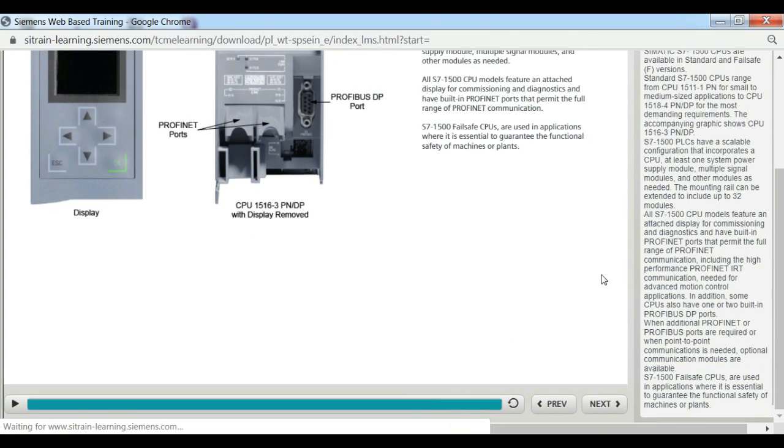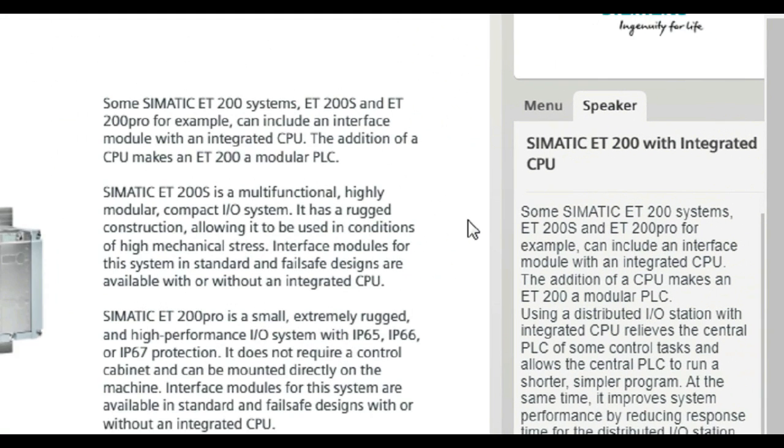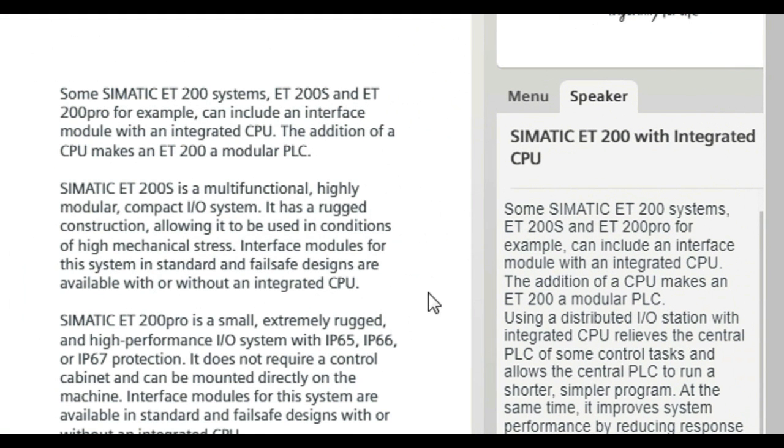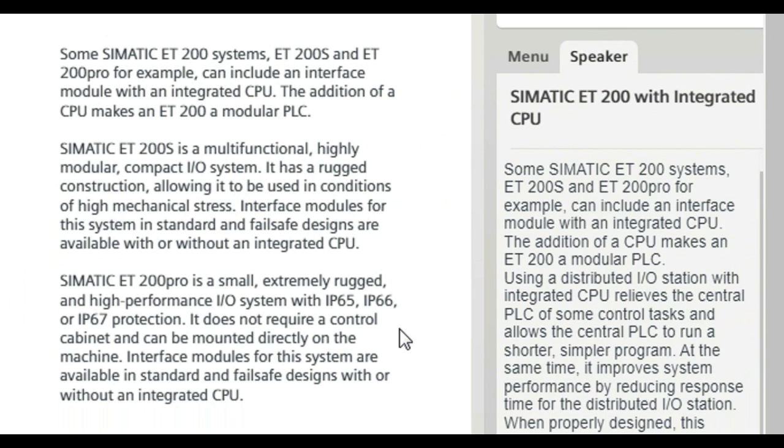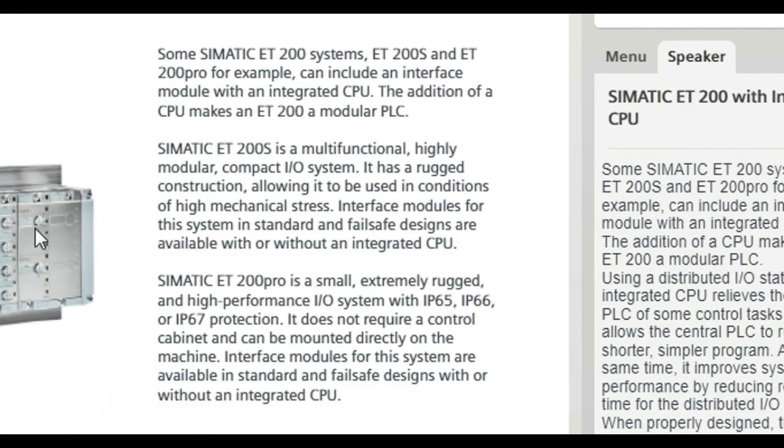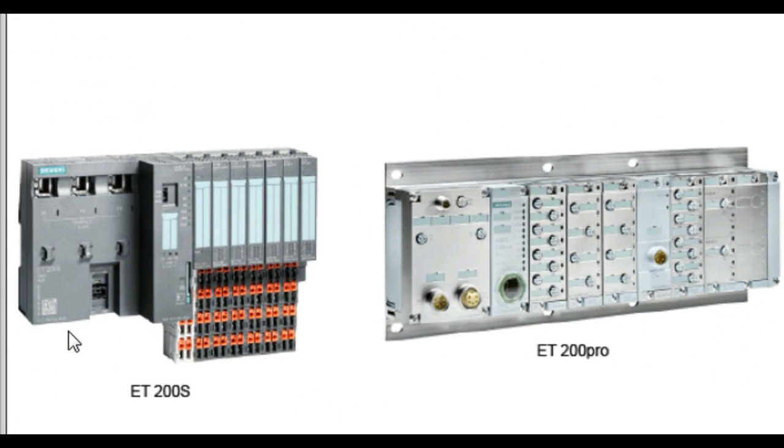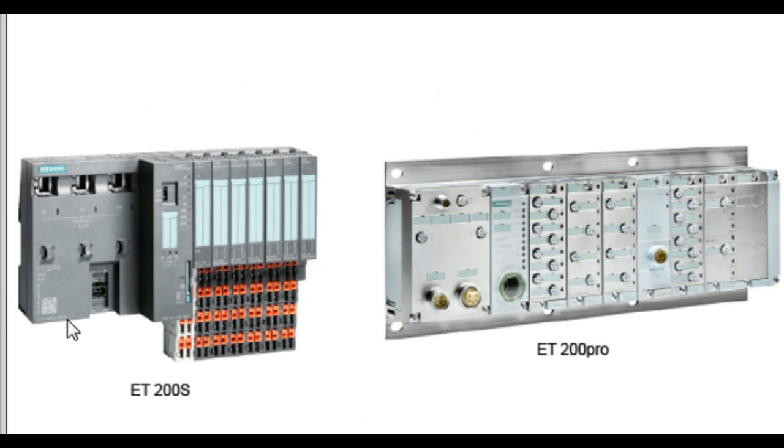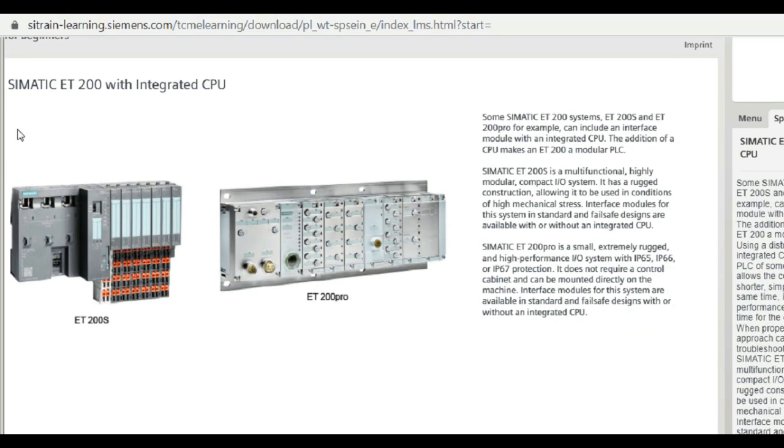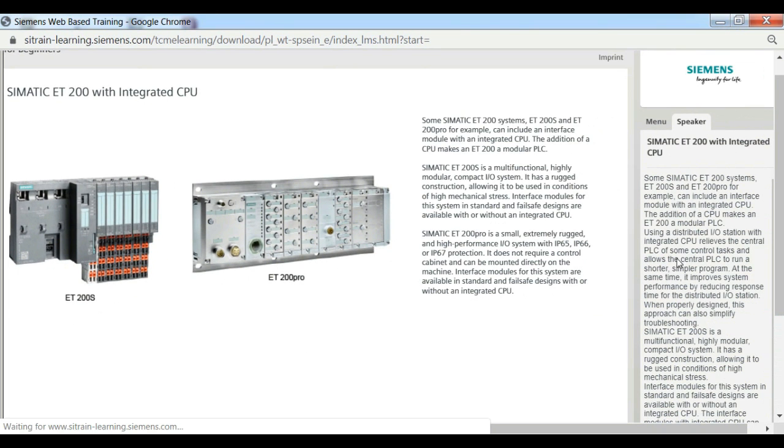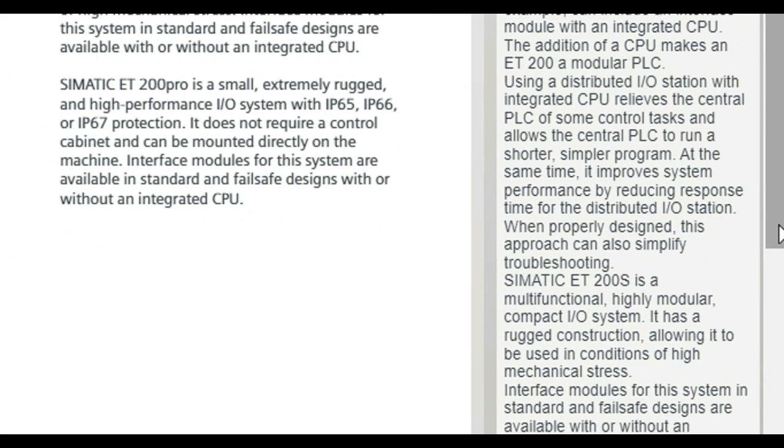Some Siemens ET200 systems, ET200S and ET200 Pro, for example, can include an interface module with an integrated CPU. The addition of a CPU makes an ET200 a modular PLC. Using a distributed I.O. station with integrated CPU relieves the central PLC of some control tasks and allows the central PLC to run a shorter, simpler program. At the same time, it improves the system performance by reducing response time for the distributed I.O. station. When properly designed, this approach can also simplify troubleshooting.